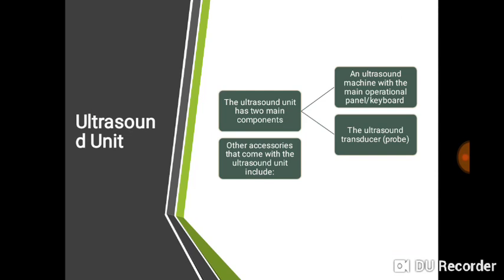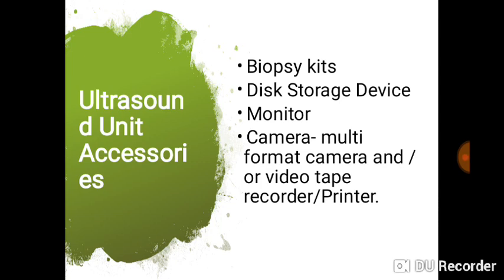A typical ultrasound machine is designed to send out sound waves into the body, and when those sound waves reflect from deep inside the tissues — based on differences in acoustic impedance — the reflected sound is received, converted to electrical signals, and displayed on the ultrasound monitor. That is what the ultrasound unit does, which is why it is made up of several components and accessories.